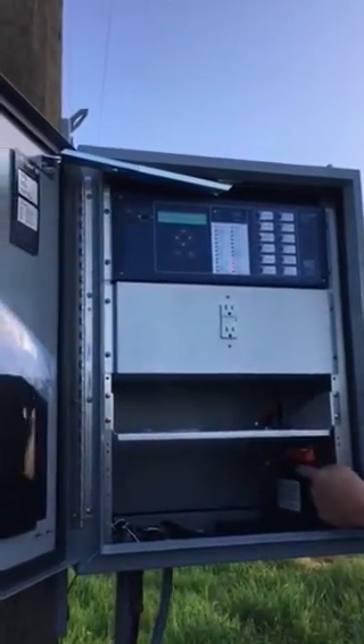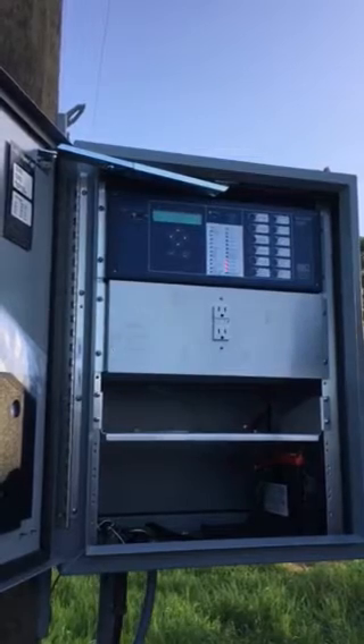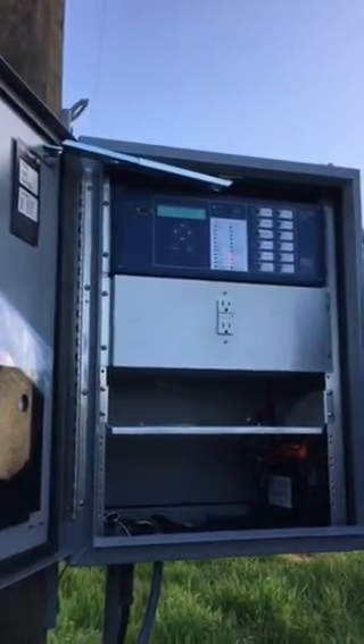We are monitoring the battery here and the AC volts coming on, so that if that fuse drops out or whatever, we should see it. So is the trip circuit strictly DC, or is it running AC until it goes out? No, all of this is DC. It keeps this battery charged. This battery is supposed to last about 16 hours after you lose power.